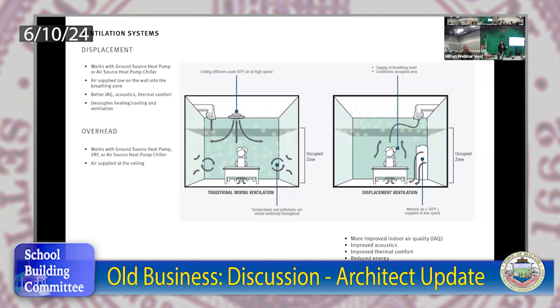Displacement has the ability to be a little bit better in terms of air quality, just because displacement is delivering the air lower. Typically it's out of the wall towards the bottom half, coming out where we're breathing, in the breathing zone. So instead of mixing the space to get comfort, it delivers air down low where we need it, and then it's exhausted up high. So it's not mixing all of the air.